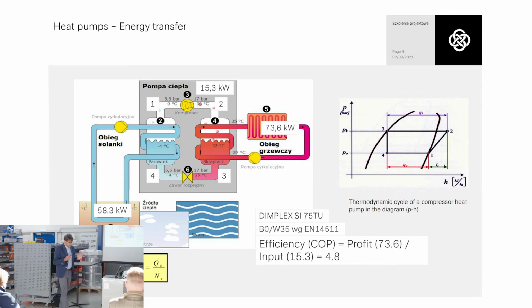An important fact is that COP is calculated in single, separated conditions, with a concrete temperature of the lower heat source and a concrete temperature of the upper heat source. There is a different factor for describing this process, the seasonal factor, also SCOP, but it is related to the whole year's production of energy. So it uses average figures, average temperatures, with different temperatures changing all the time on both sides.